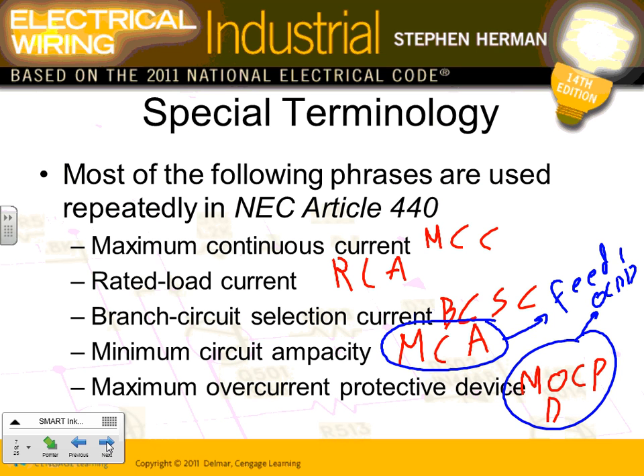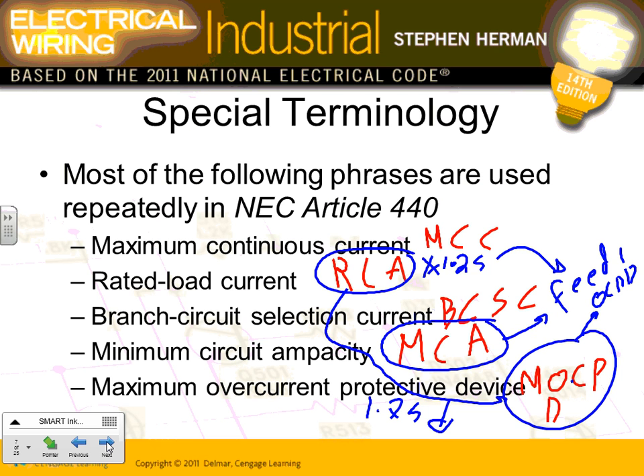By code, the manufacturer of a chiller or compressor equipment, which they call hermetically sealed equipment, has to put these two on the nameplate so you don't have to do a calculation. If they don't, then you use the rated load amps and multiply it by 1.25, and that will size your feeder. And multiply the rated load amps by 1.75, and this will size your overcurrent device, and you go down. Any questions, guys? Any comments? So that's what I want to emphasize, the most important thing about it.